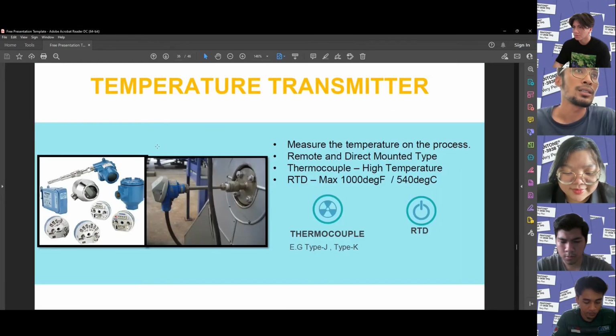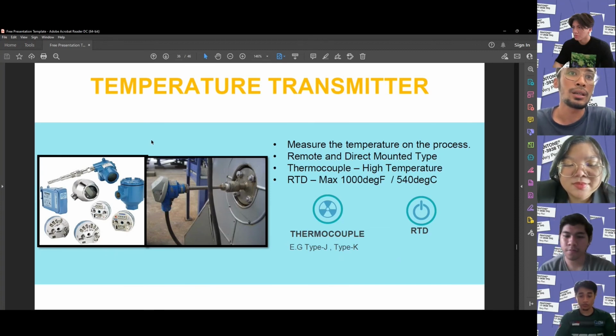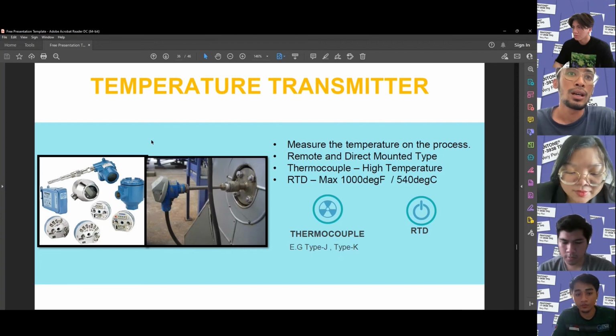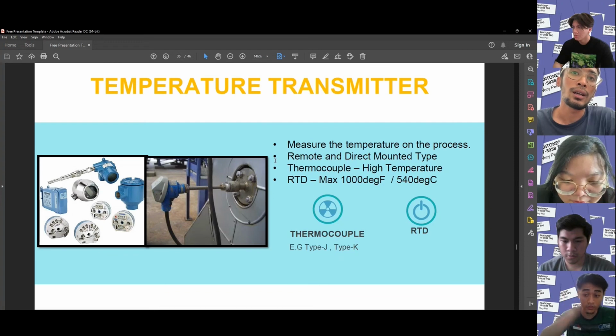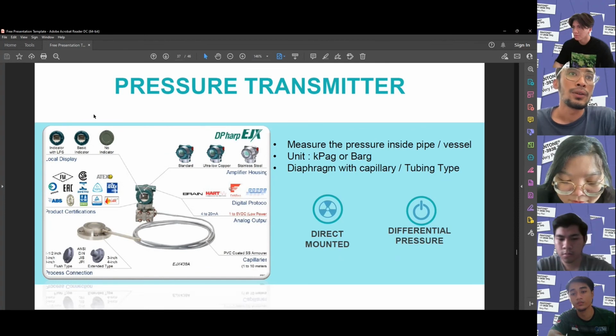Next. Okay, next is the temperature transmitter. There are 4 points here: measure the temperature of the process, remote and direct mounted type, thermocouple for high temperature, and RTD, max 1000 degrees Fahrenheit or 540 degrees Celsius. Pressure transmitter. First, it measures the pressure inside a pipe or vessel. The unit is kPag or barg. The diaphragm is with capillary or tubing type.